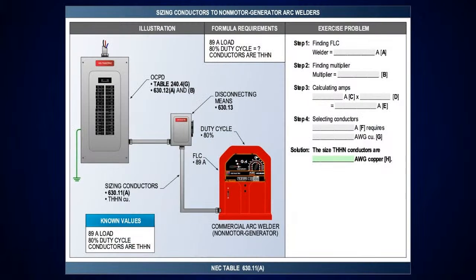Okay. And then you come over here. Here you have a commercial type arc welder. We've redrawn these too. And you're going to see we have an 89 amp load and an 80% duty cycle. Step one, you've got your welder, you know it's 89 amps. Then all you need to do is look at table 630.11(A), pick up the 80% duty cycle, come across, get your multiplier, do your calculation, and size your conductors.